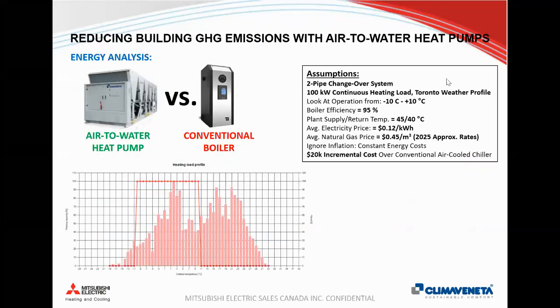So this is just looking at a comparison between air-to-water heat pump and conventional boilers. Typically, this is an example for a two-pipe changeover system. This is also using some approximate rates that I forecasted that I would expect around 2025, because something has to happen to the price of natural gas versus electricity so that heat pumps can be more widely implemented. Maybe part of that will be special electricity rates if you're using a heat pump for heating in large commercial buildings. Who knows? But for this example here, this is just assuming a two-pipe changeover system.